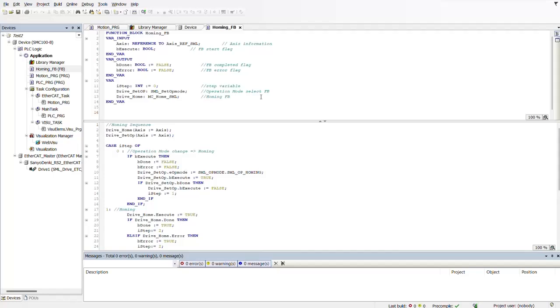The error command is basically to indicate whether an error occurred during the homing procedure or not. Then we have our local variables — we have an integer variable used as a step counter to manage the process of the homing procedure. Then we have our drive_setup, which is likely a function block used to set the operation mode of each axis, such as velocity, positioning, or homing. And lastly we have our drive_home — this is the motion control function specifically designed for homing operations. This block will contain the logic and parameters necessary to execute the homing as a sequence.